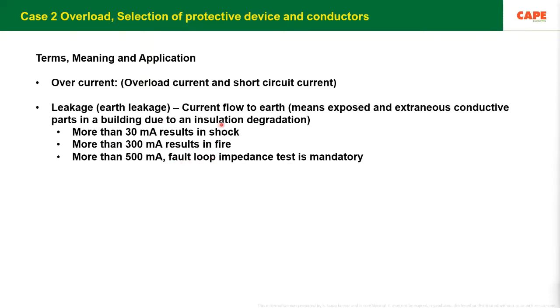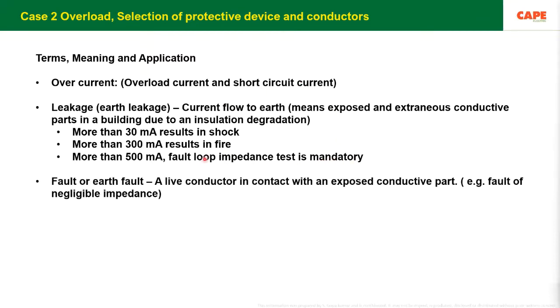So there are 3 subjects with respect to earth leakage. To prevent an accident because of earth leakage, you need an RCD or RCCB of 30 milliampere for shock protection, up to 300 milliampere for fire protection, and up to 500 milliampere if you want to avoid a fault loop impedance test. So this is how you are supposed to do overload protection.